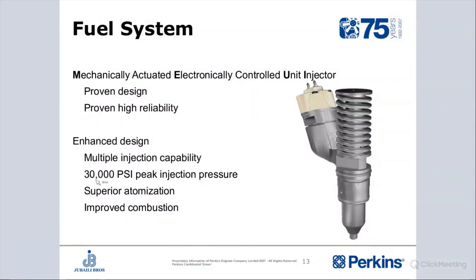30,000 PSI is the maximum fuel pressure we get from the injectors, whenever the engine is running at 60 Hertz full load. That's how much pressure we might get.